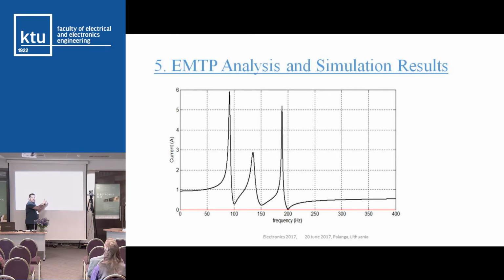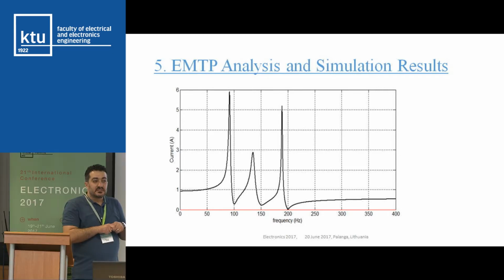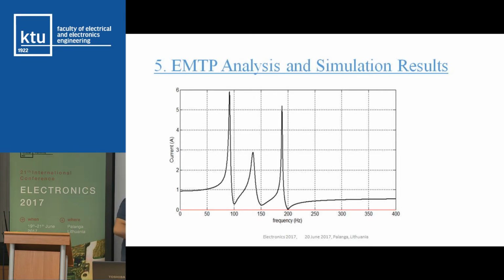this would be caused by the electric arc furnace. But in this case the arc furnace load is not included in the system, and I don't have any load, and I am checking my SVC system and harmonic filter performance, and we can see here that even harmonics are a big problem, and my harmonic filters are modeled very well. As a result, I can say that this is the result of the SVC system only.